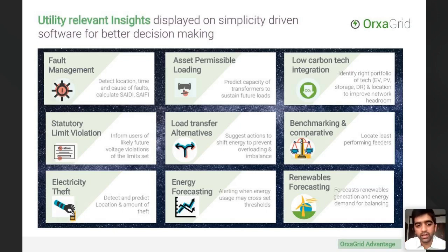Through that, we understand how much loading customers or grid companies should do on their individual assets. Taking that logic further, once we understand when assets are in overload conditions, using the Synapse model we can also predict or do a life estimation on that transformer. Residual life estimation is a lot more complex, but this feeds in as one of the multivariable inputs for the RLE of each asset. For the RLE, we also look at historic faults, the types and materials of the assets, and so on.